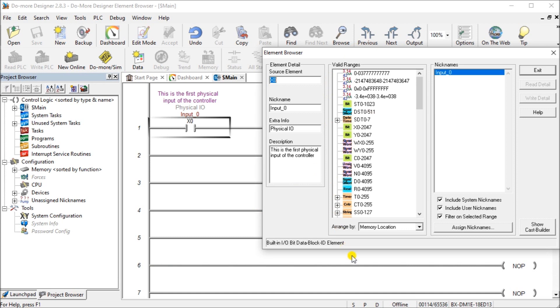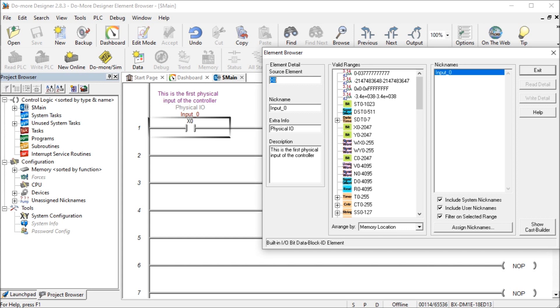We also have valid ranges which are located right here and it displays a list of the valid ranges of elements for the current content and how the element browser was invoked controls what displays in the valid range list. So select mode. This mode is enabled by clicking the magnifying glass icon while editing an instruction or pressing the F9 key while in the ladder editor. In this mode, the element browser used as a guide in selecting a valid controller data element for the instruction you are editing. Since the element browser was called from the ladder editor, the ranges of the elements display will be correct for the current instruction. And then we have a browse mode and this mode is enabled by opening the element browser from the menu or clicking the magnifying glass icon on the toolbar. In this mode, the element browser used to display the complete list of the ranges for the current controller. Instead of the select button, there is an exit button.